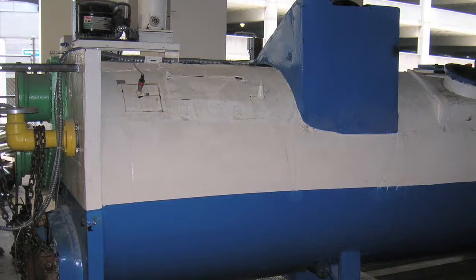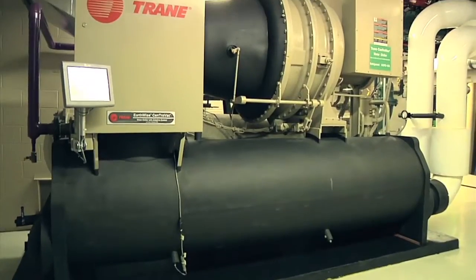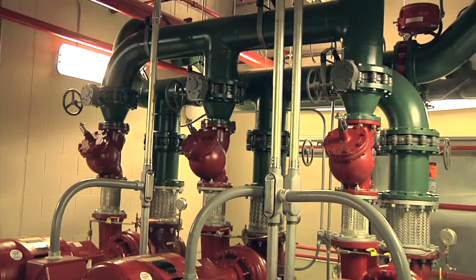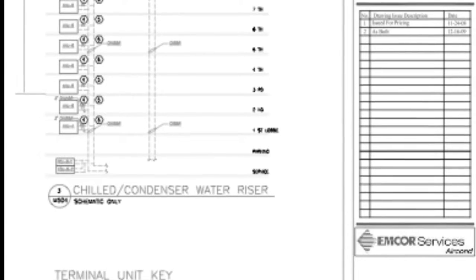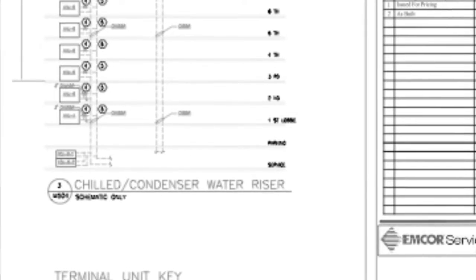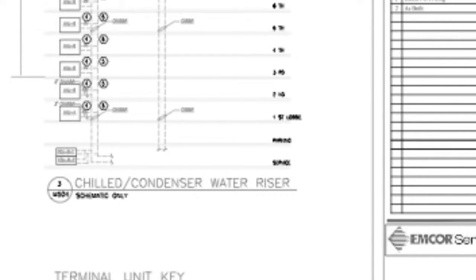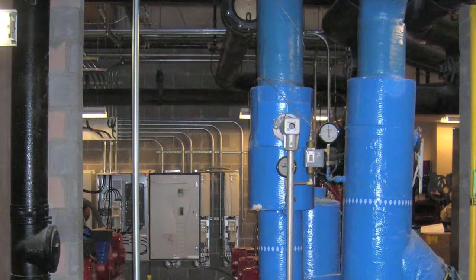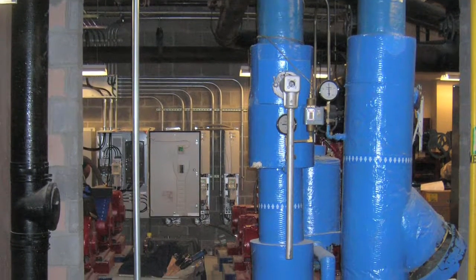Their chillers were nearing the end of their useful life. So we took that opportunity to replace the chillers with some more efficient equipment to retrofit it to a primary-secondary system and also increase the capacity of the central plant. The original design had chillers piped in series. There were a series of constant speed pumps that were not able to match the load of the building and also provide adequate cooling to the top floors.